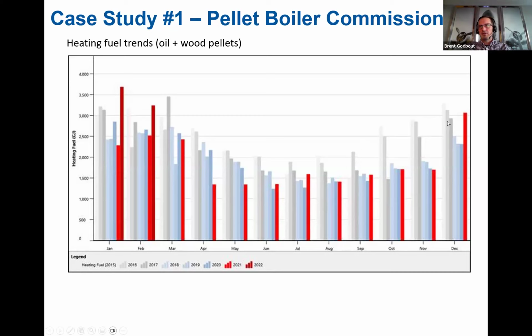The first drop back in here, this is like 2016, 17, we did a big recommissioning project, which is why you see the big drop in energy in following years. So that's what that first big drop is. But then once we commissioned the boiler, we're almost back to what we were using before, which isn't what we wanted, obviously. Then leading into 2022, this duller red line here is 2022, so that's January and February. We're definitely using a lot more energy. It's not what we wanted.